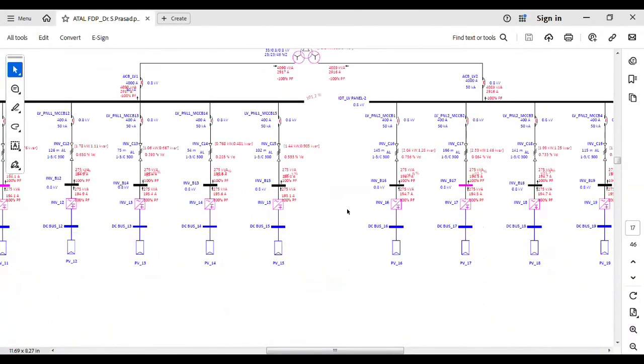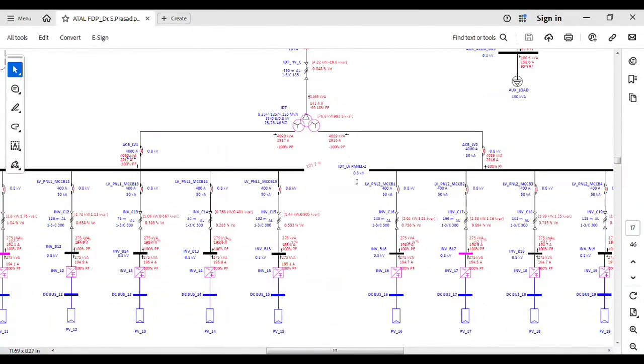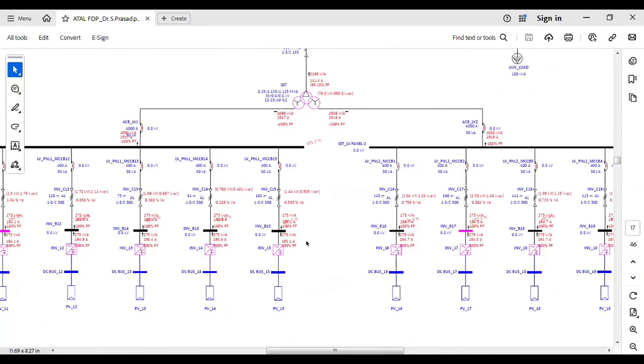As I mentioned, one IDT transformer is there, of capacity 8.25. This is a 3-winding transformer, and we have modeled the solar plant. In this solar plant there are 30 string inverters, and each inverter capacity is 275 kVA. So 275 into 30 gives you the total capacity of the plant.